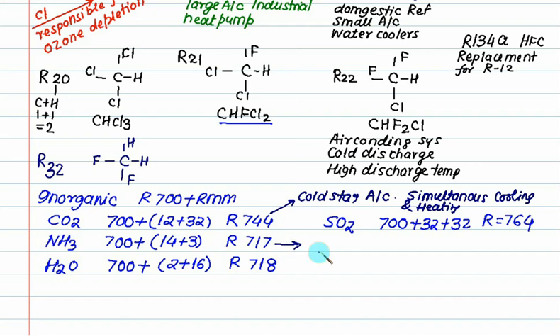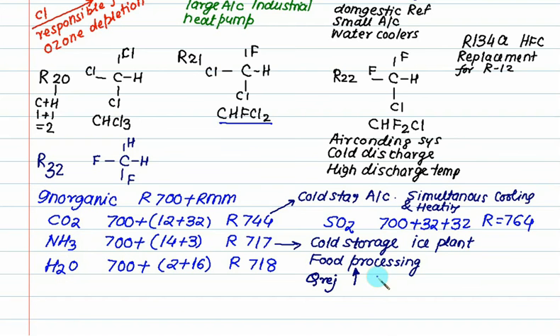R717, that is ammonia, is for cold storage, ice plants, and food processing industry. Heat rejected in ammonia compressors is very high, so ammonia compressors are normally water-cooled. Extra heat is carried by water jacket.